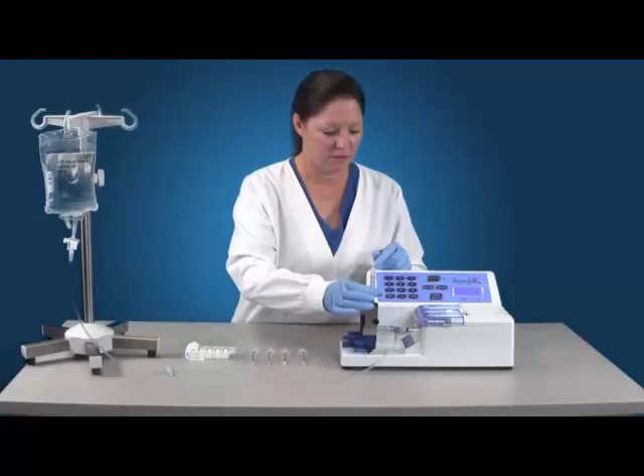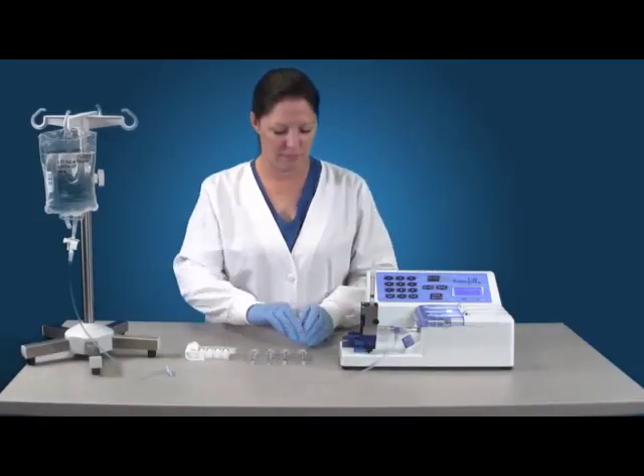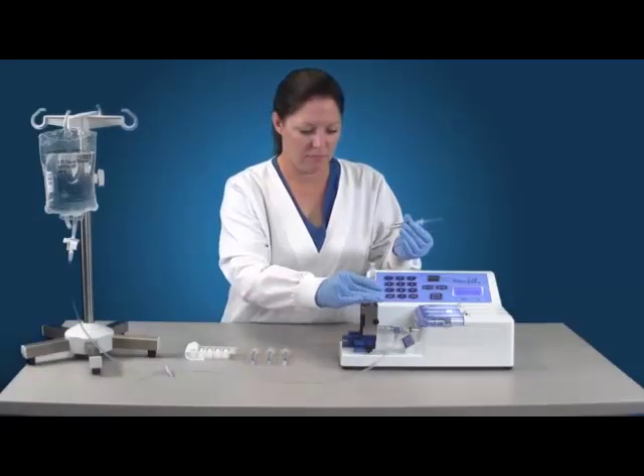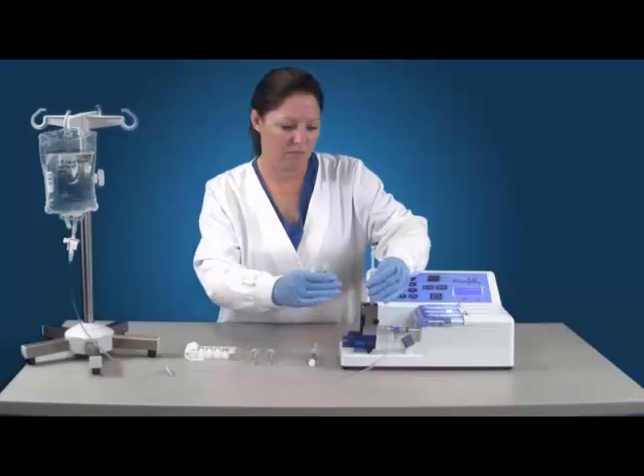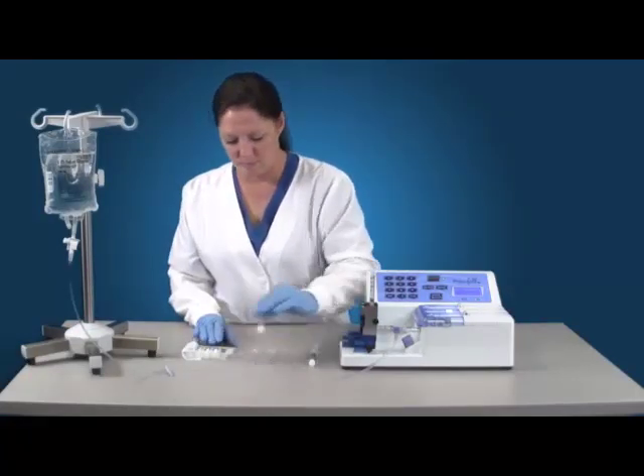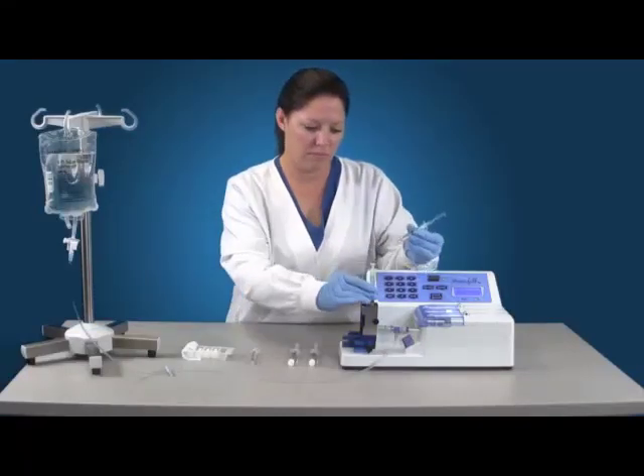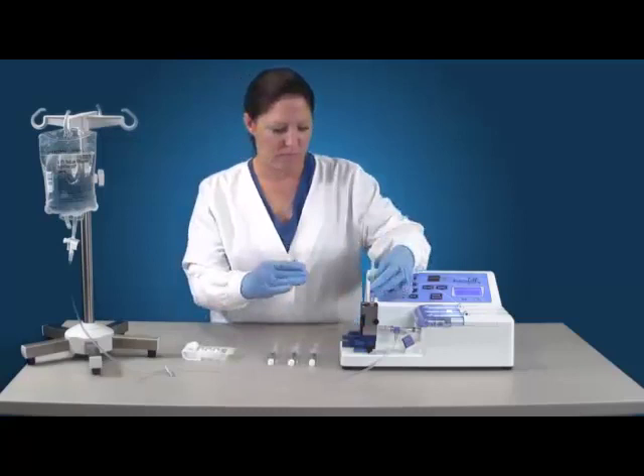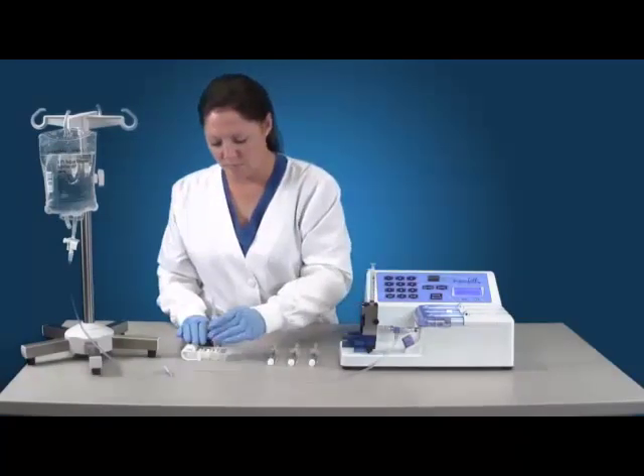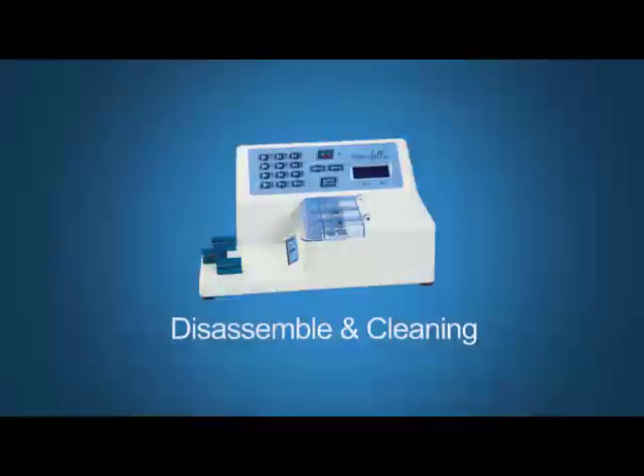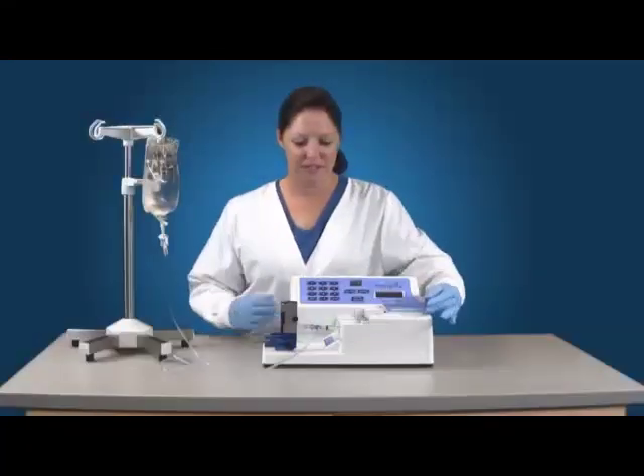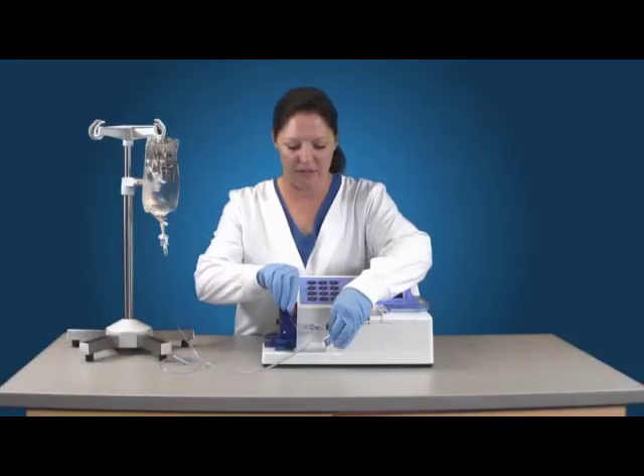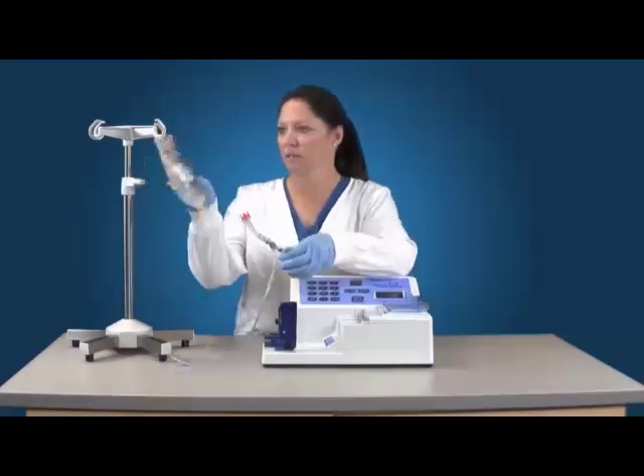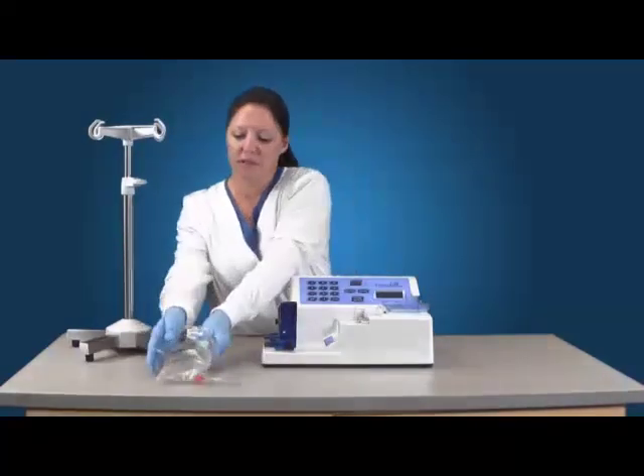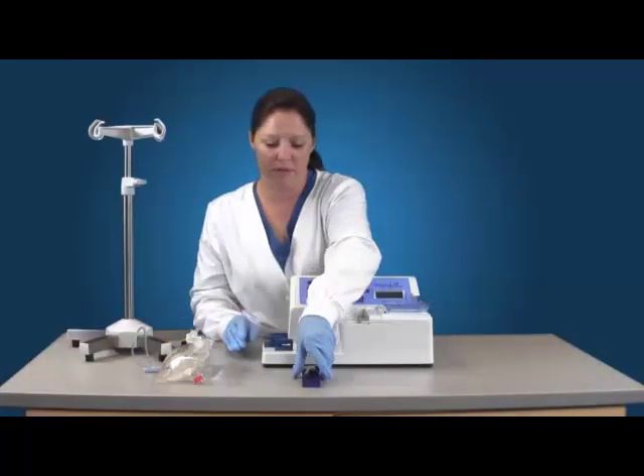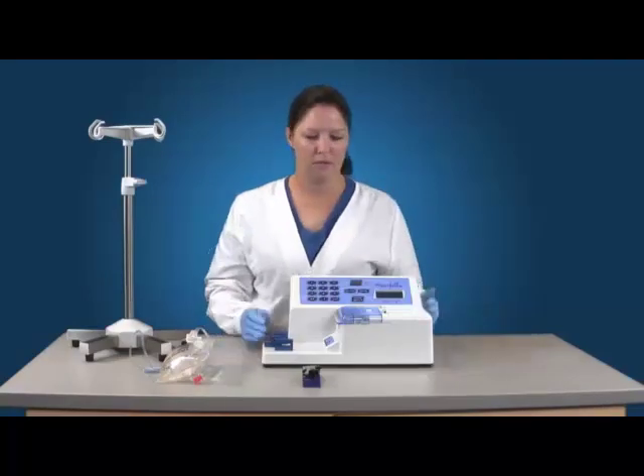Lock the target syringe in the adapter. Press Start-Stop to begin the filling process. When the target syringe is filled and the cycle is complete, remove it from the adapter, replace it with another unused target syringe. Verify the fill volume of the filled syringe and place a cap on it. Repeat these steps for all cycles. To halt production at any time, press the Start-Stop button. After production is complete, remove the tubing set and syringe from the pump and discard into appropriate waste container. Thoroughly clean the block holder and pump with Approved Clean.